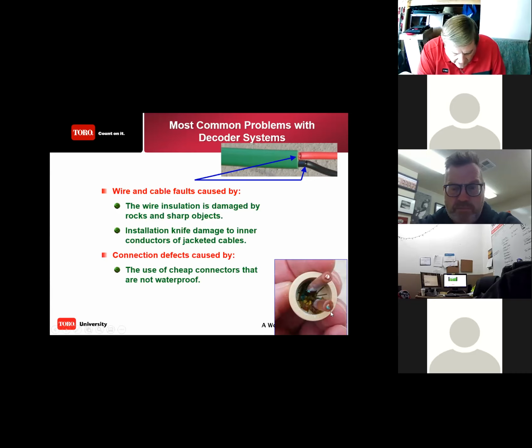Use the proper connector. Look at this one. You can see the green corrosion on the surface of the wire. You can see the green corrosion inside the wire connection, right there. The proper connector: this is a good connector for the valve wiring to the solenoid, but not on the 2-wire path. It's not designed for the higher current draw.